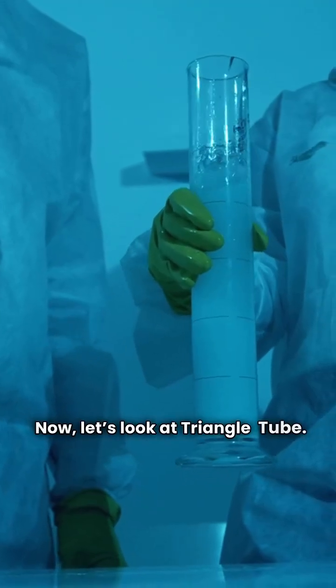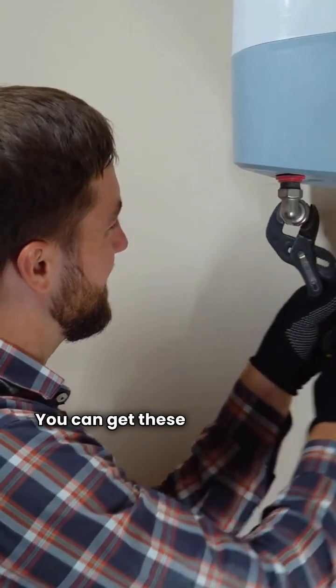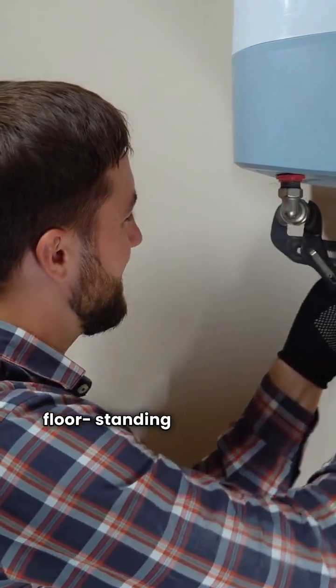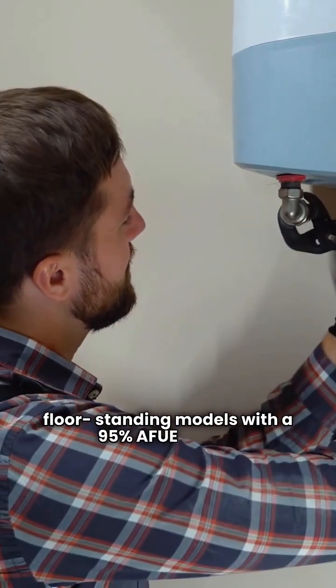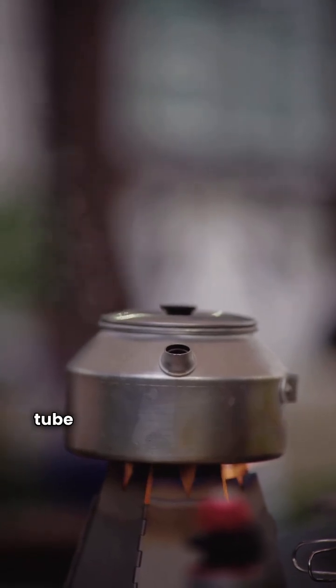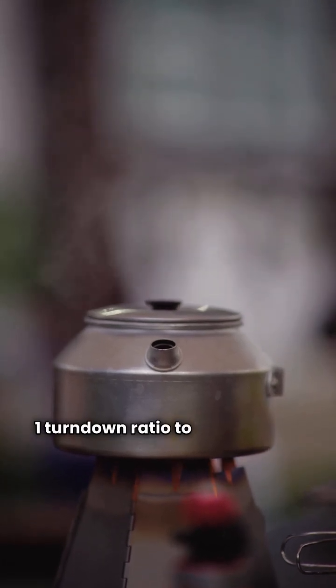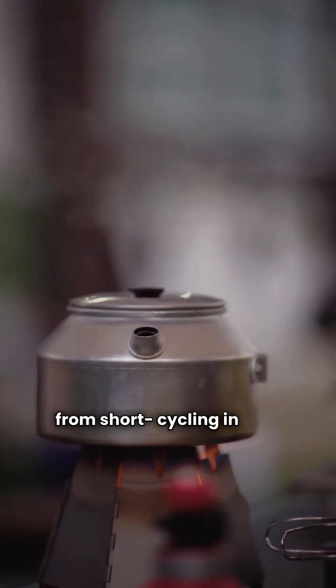Now, let's look at Triangle Tube. Their Instinct Series is all about keeping things simple. You can get these in wall-hung or floor-standing models with a 95% AFUE rating. They use a 439 stainless steel fire tube heat exchanger and boast an 8.1 turndown ratio to stop the unit from short cycling in mild weather.